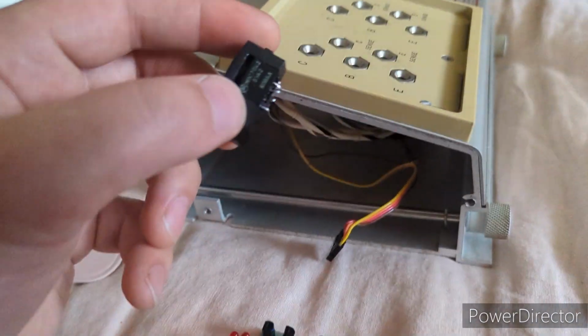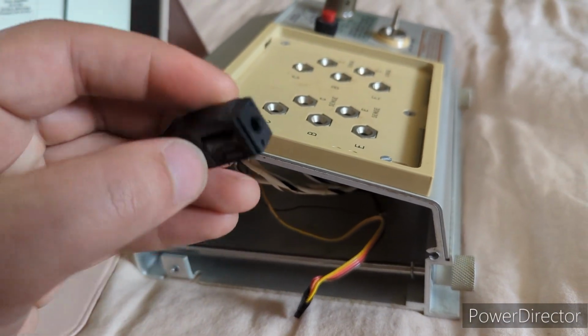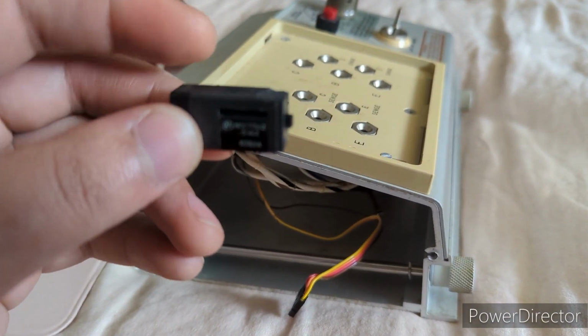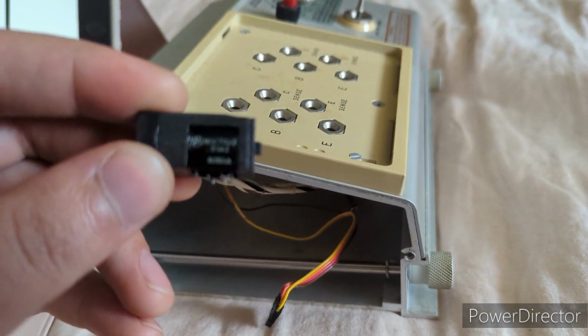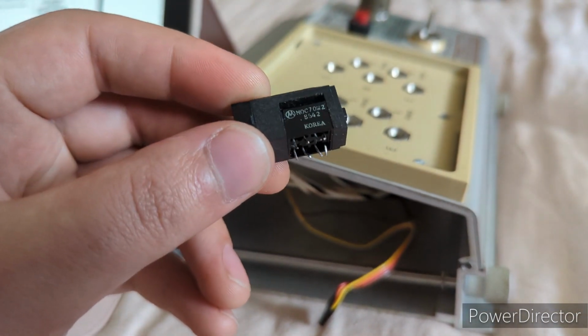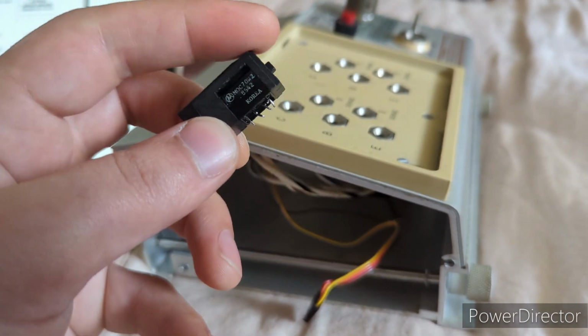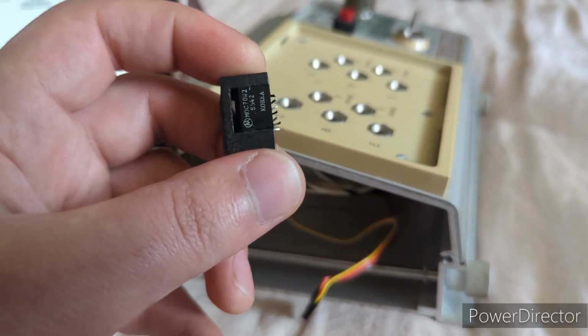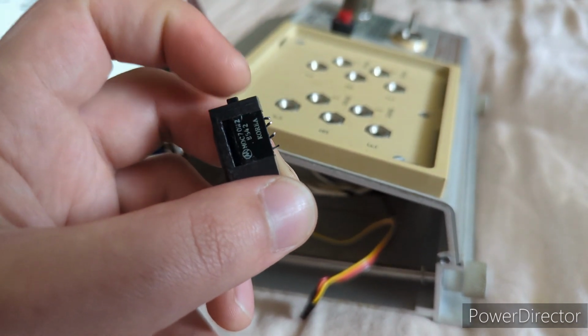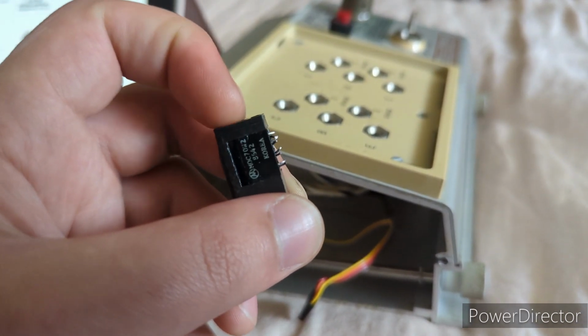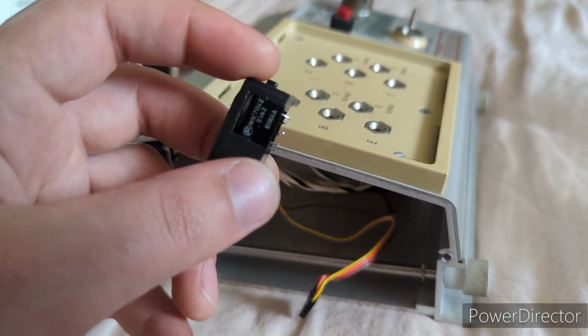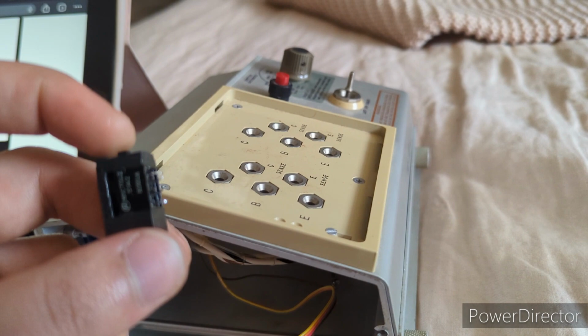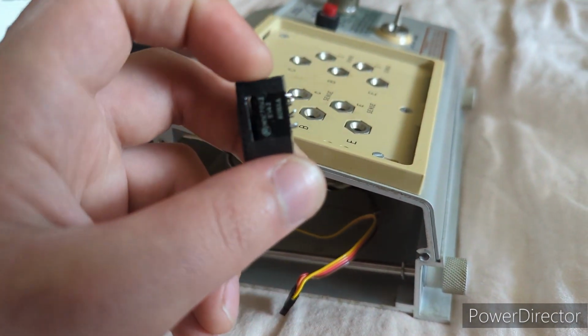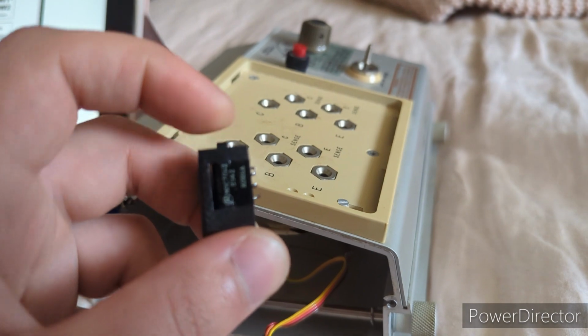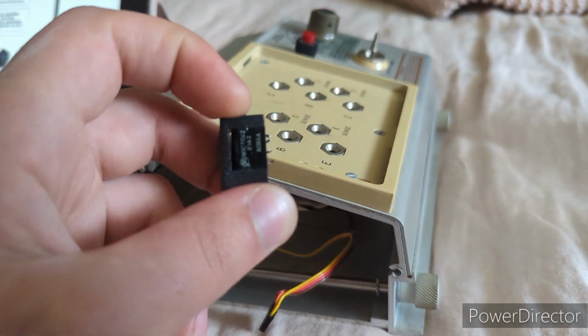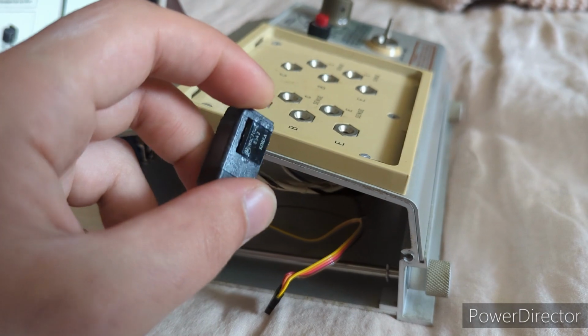So I wanted to figure out how I can bypass this. This guy's pretty unique. I haven't ever seen one of these before. It kind of threw me off. In fact, initially, this guy was stuck already in the closed position, which was already an indication that this guy must be faulty, because it was still disabling the high voltage for me. So I did put some contact cleaner on it to get it to open and close.